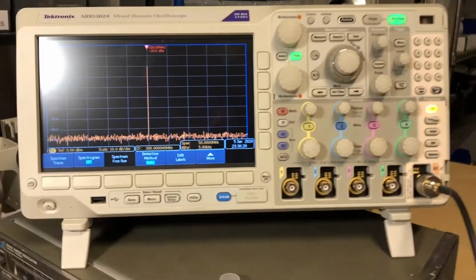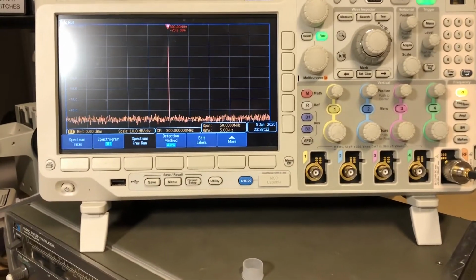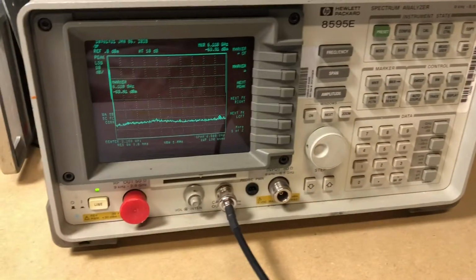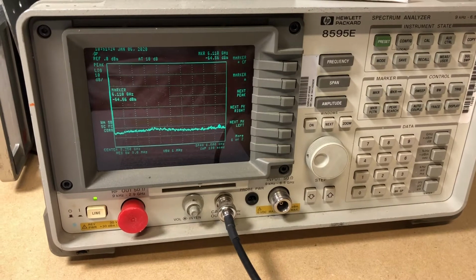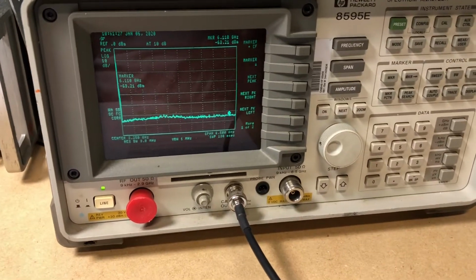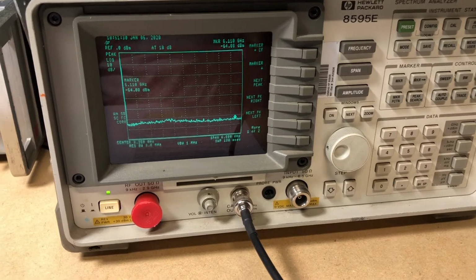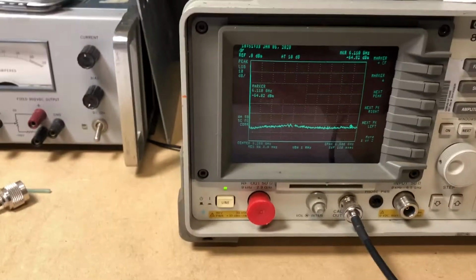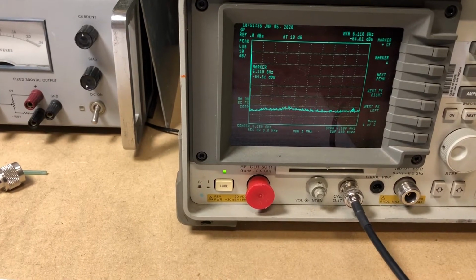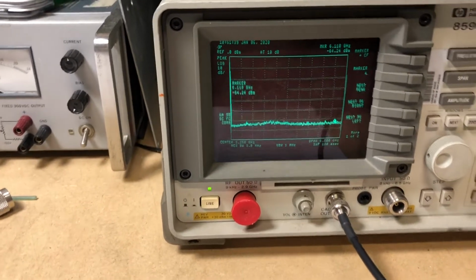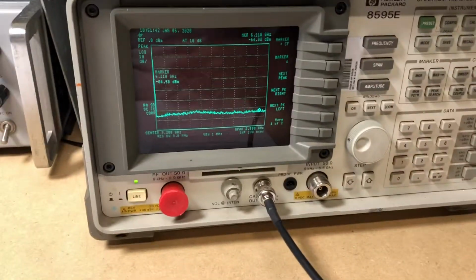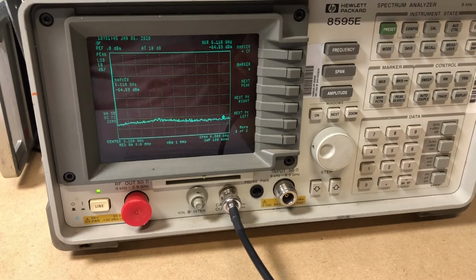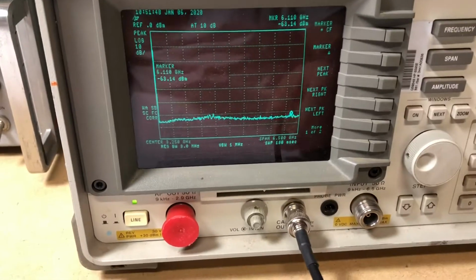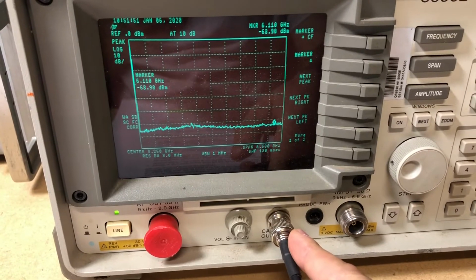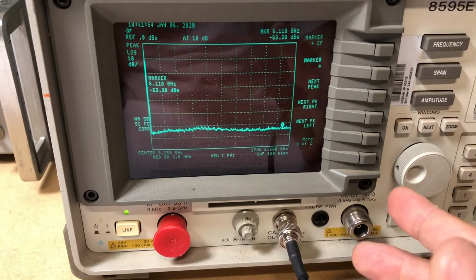another spectrum analyzer. See if I can get this glare off the screen. The reason I'm using the spectrum analyzer is if you read the service manual, it talks about taking RF power level readings inside the unit, and this one in particular, it tells you specifically not to use wideband power sensors like the sensor I used earlier for the demonstration, the 8481A sensor, because a lot of the signals in this unit have harmonics. This one in particular is specifically set up to have a lot of harmonics, and those harmonics will throw off your power level reading.